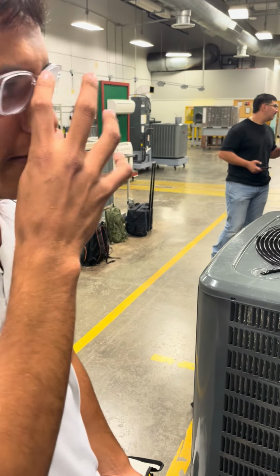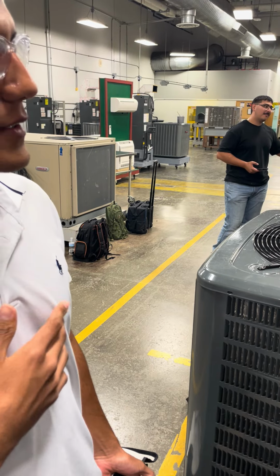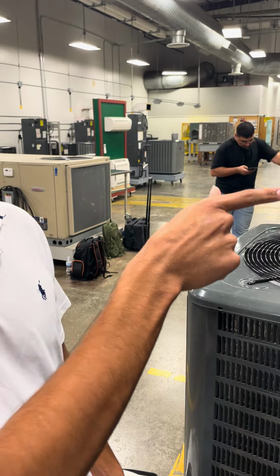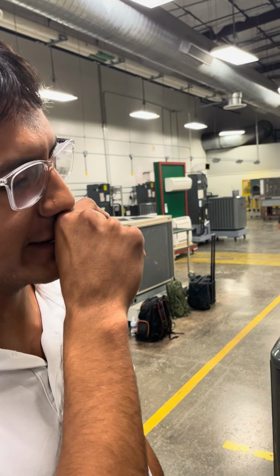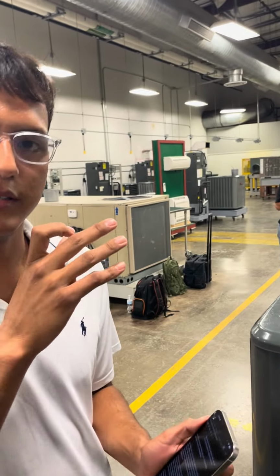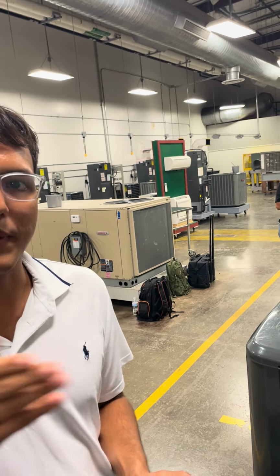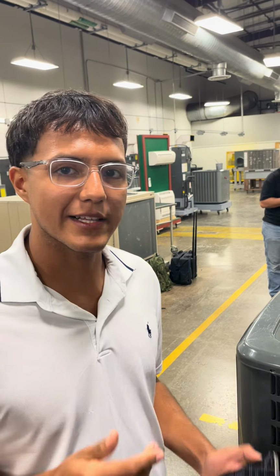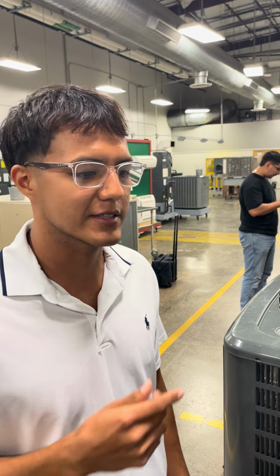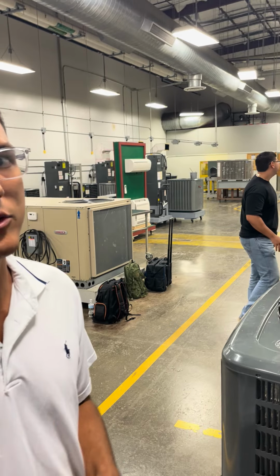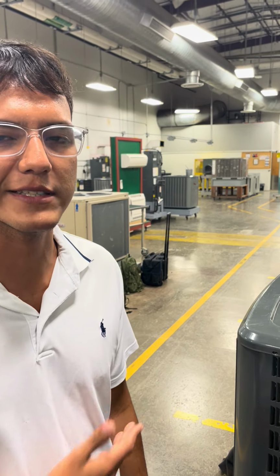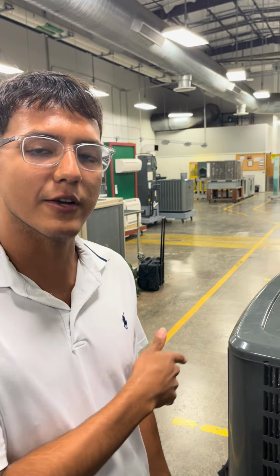And when you're getting your air filters and figuring out how you want to do it, you got to look at the manual for the condenser, air handler. You want to look at the manual for the air handler, and it'll tell you the length by width by height of what type of filter you need. And there's also the MERV rating, which on most residential systems you want 8 to 11 because they're still good for filtration, but they're not too much. The MERV scale is 1 to 20, and the higher ones are more for bacteria and stuff like that, and you don't want to restrict too much airflow to the unit.